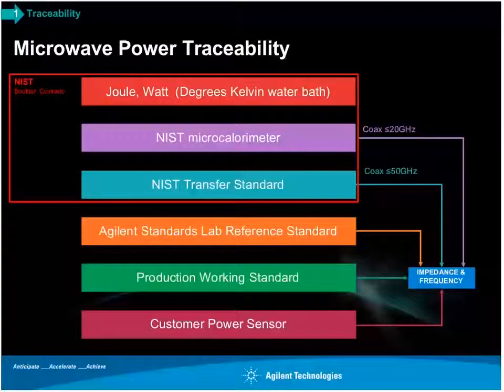So that starts out as a NIST transfer standard, and then for Agilent, we send in our reference standards to either NIST, or oftentimes we send them to the National Physics Laboratory in the UK, who also is at this top level. And that would be our reference, and then from there we use that.